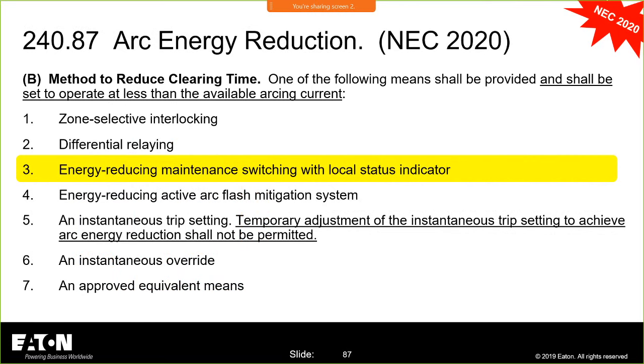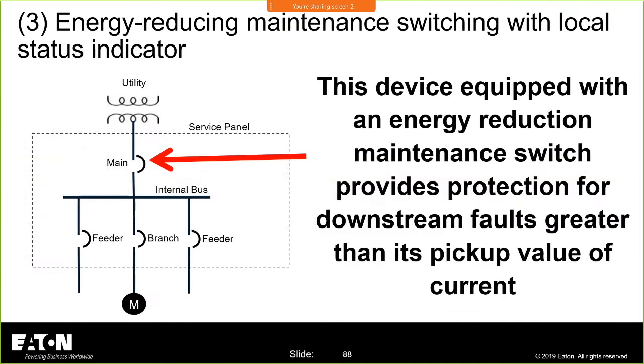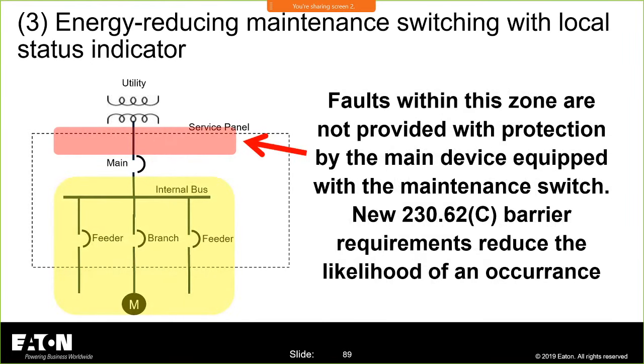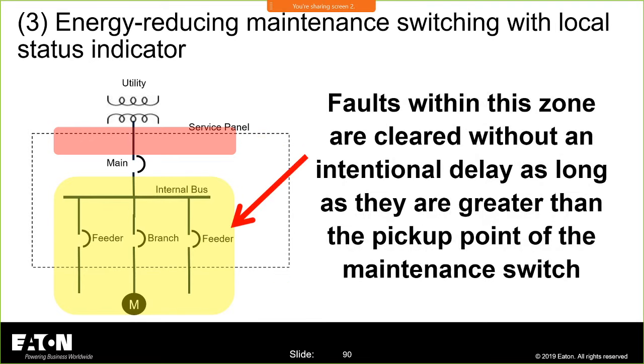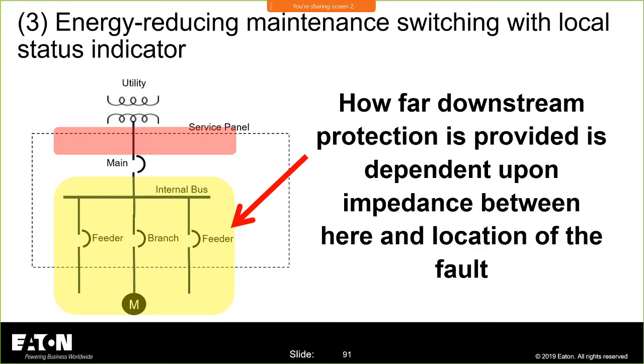Now, the energy reduction maintenance switch with local status indicator. That'll give you the protection downstream. We already talked about that. Same method, same technology used on fuses. Okay. How far downstream? It depends upon the impedance.